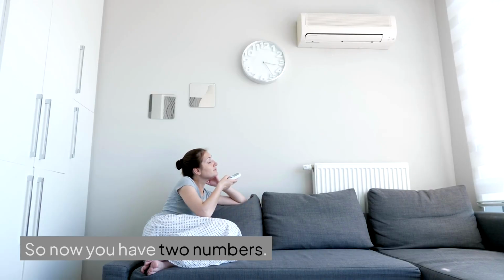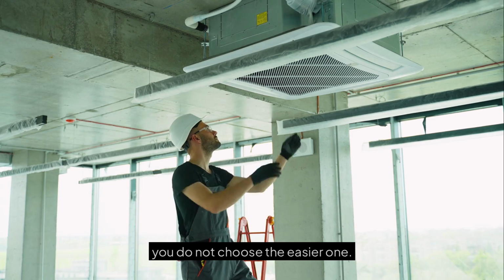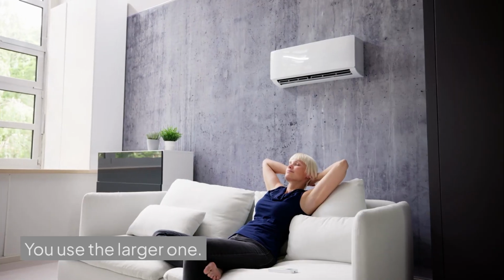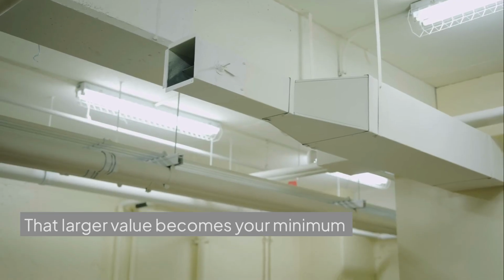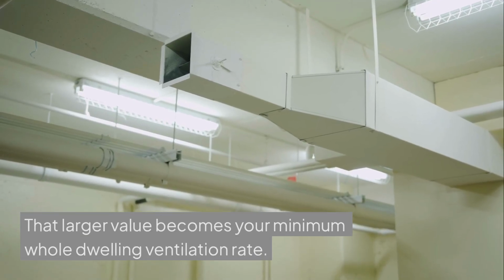So now you have two numbers. And this is the main junior engineer takeaway. You do not choose the easier one. You use the larger one. That larger value becomes your minimum whole dwelling ventilation rate.